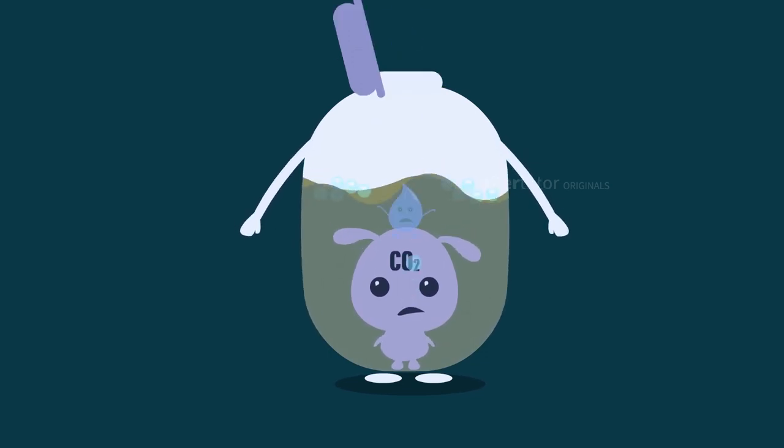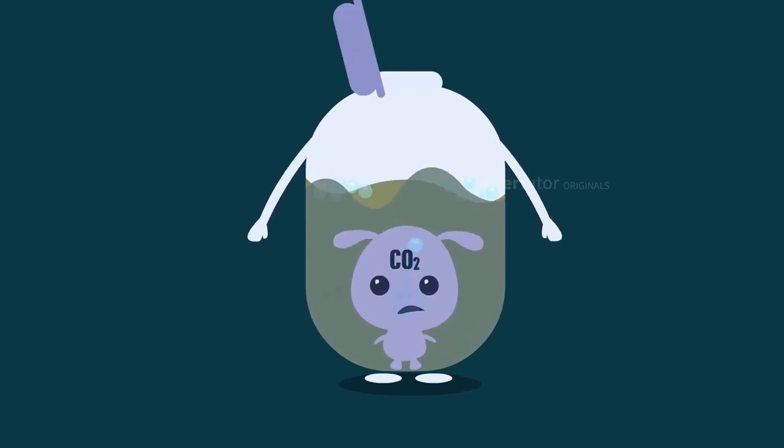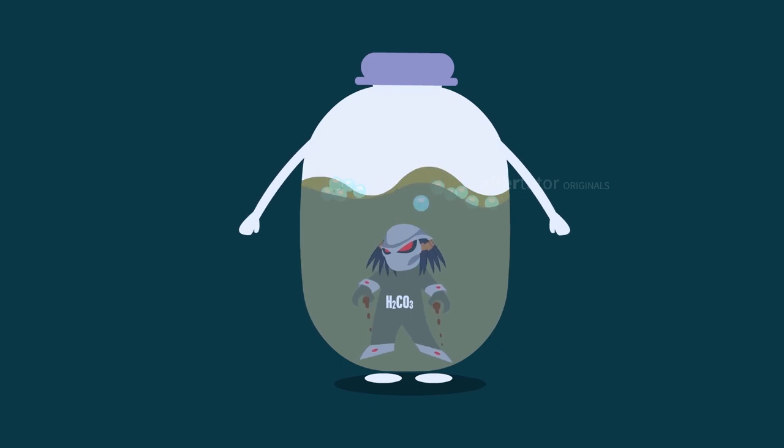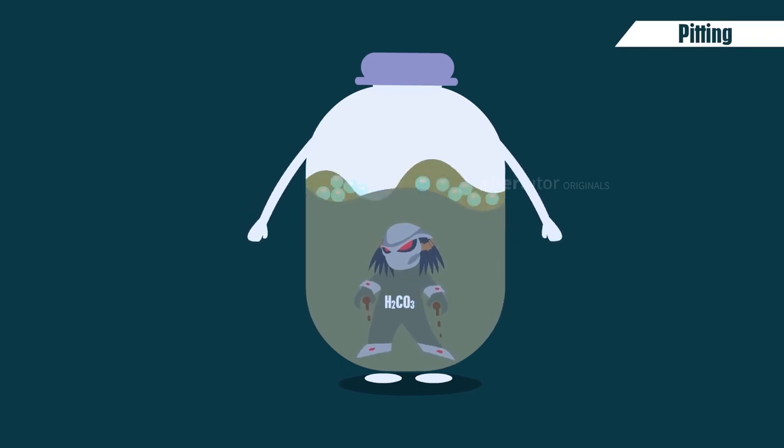Carbon dioxide, when reacts with water, forms carbonic acid. The formed carbonic acid causes corrosion in the boiler, which is called as pitting, nothing but the localized form of corrosion.